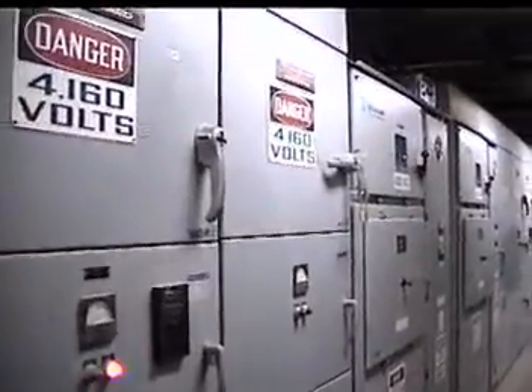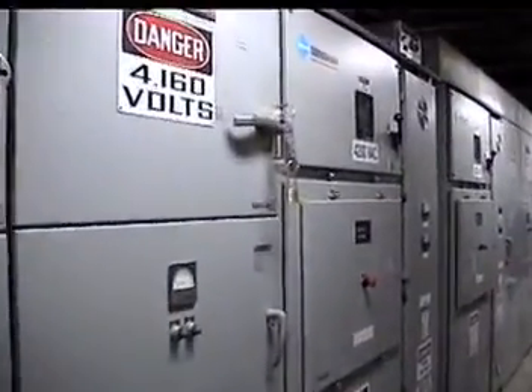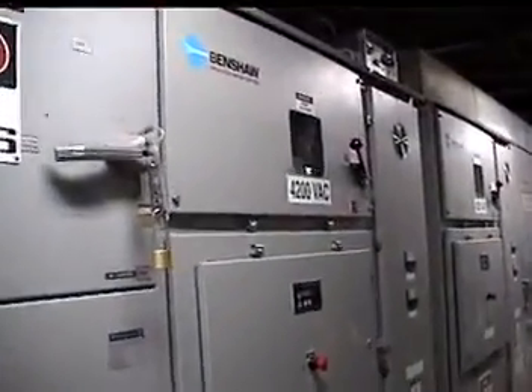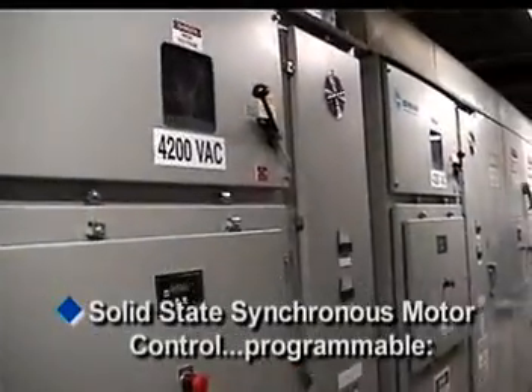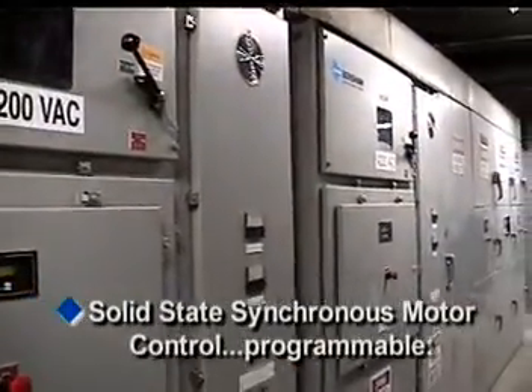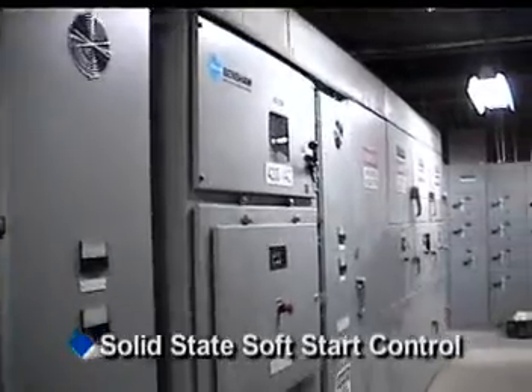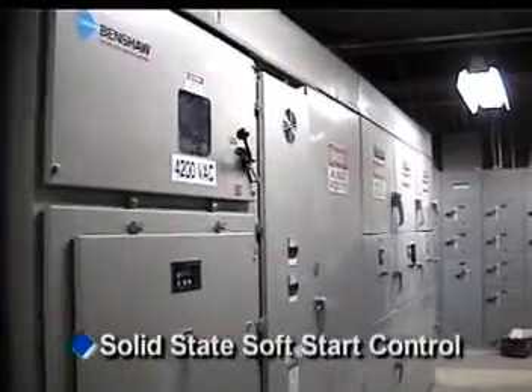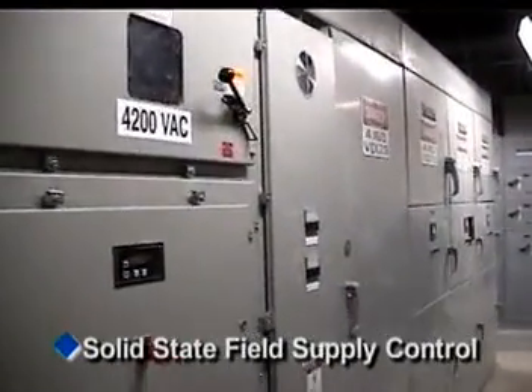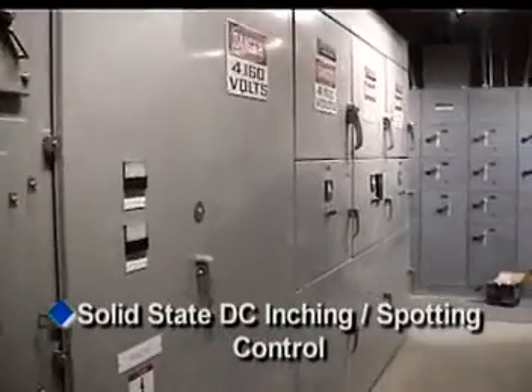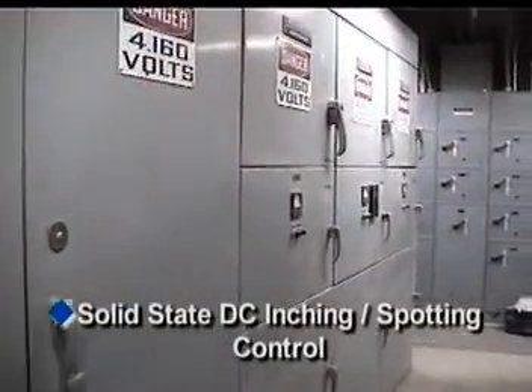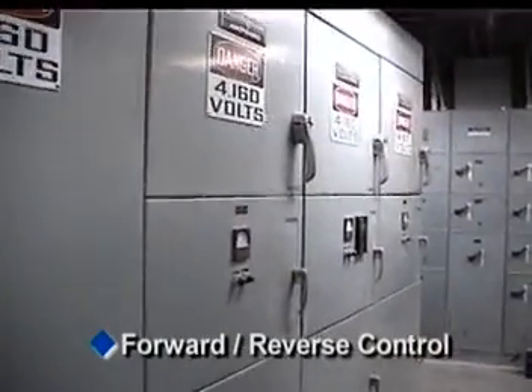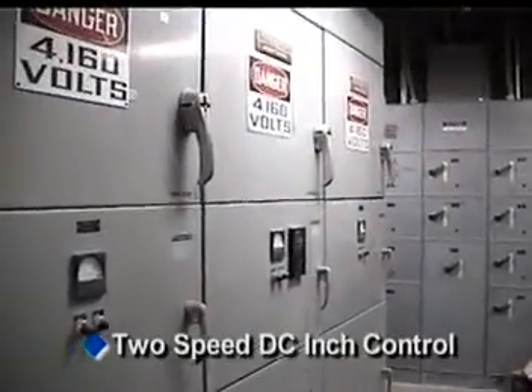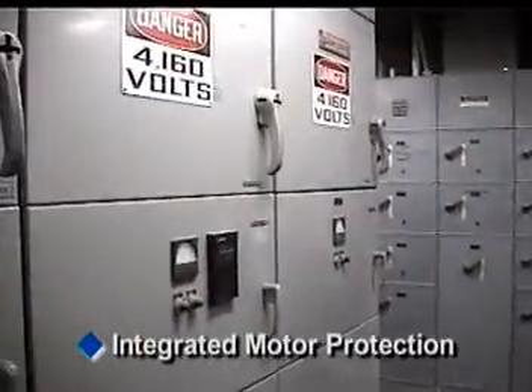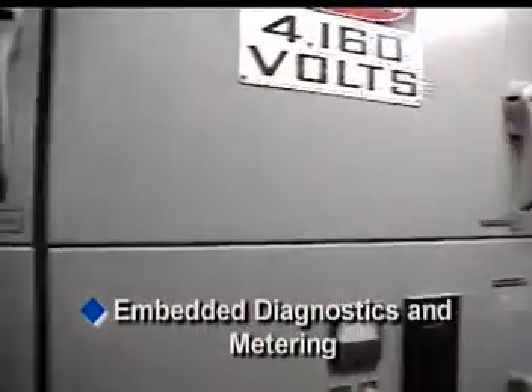They are designed to easily fit within existing space limitations and feature solid-state synchronous motor control, programmable solid-state soft start control, solid-state field supply control, solid-state DC inching and spotting control, forward reverse control, 2-speed DC inch control, integrated motor protection, embedded diagnostics and metering.